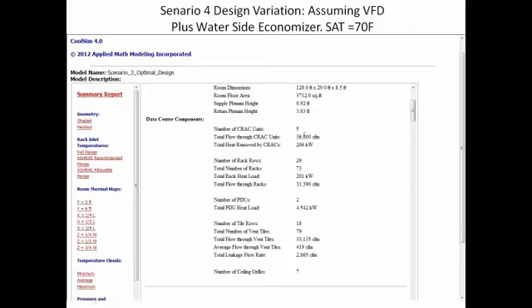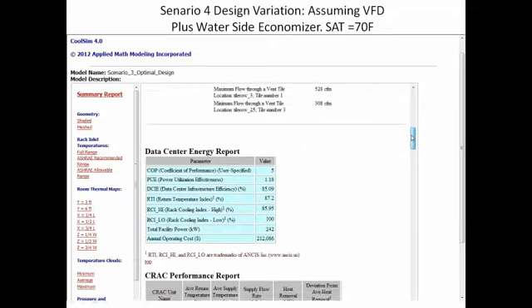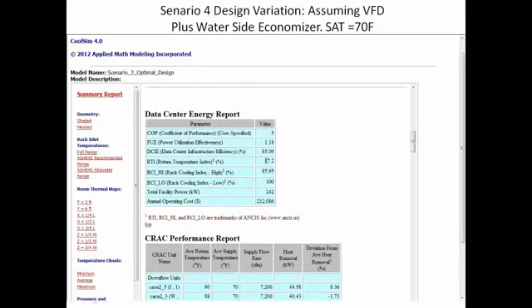You see now we're down to 36,000 against a requirement of 31,000. So we're getting very close here to being optimal. And if we take a look, now our RTI is at 87%. So we're getting there. Now you do sacrifice a little bit, and I also pushed supply air temp up a little bit here too. And you see that my RCI high began to come down a little bit, which means I'm getting hot in a couple places. But look at my RCI low, 100%. So this means I'm saving a tremendous amount of energy in fan speeds and fan power.